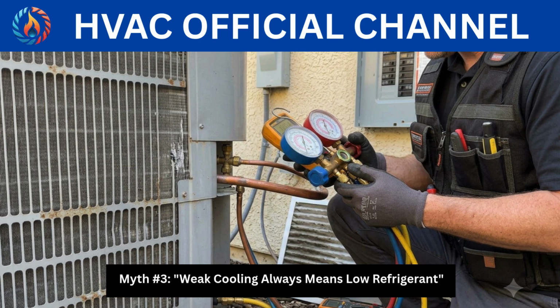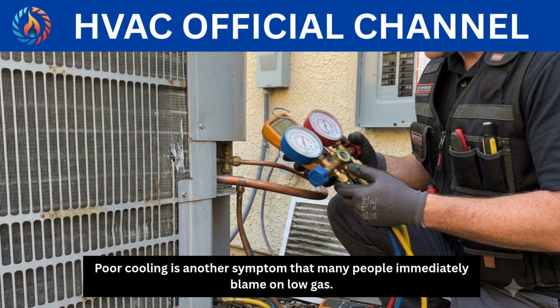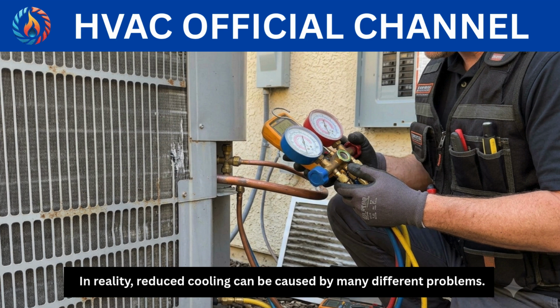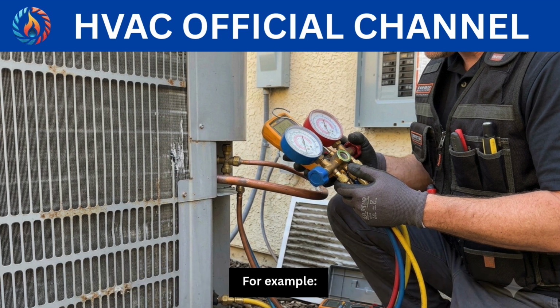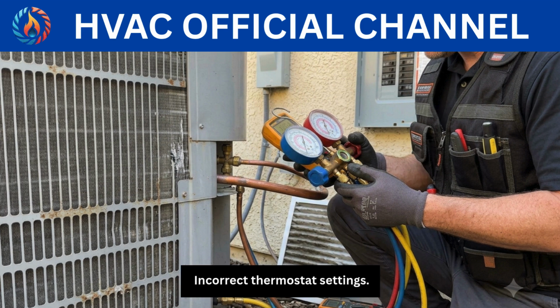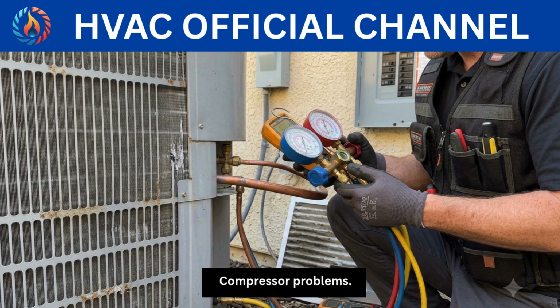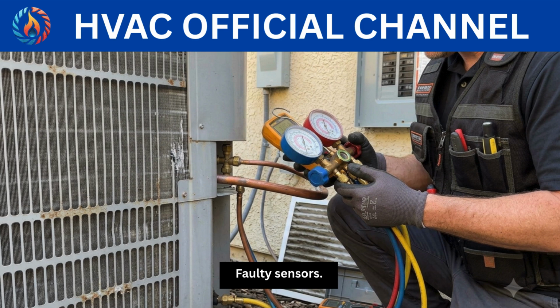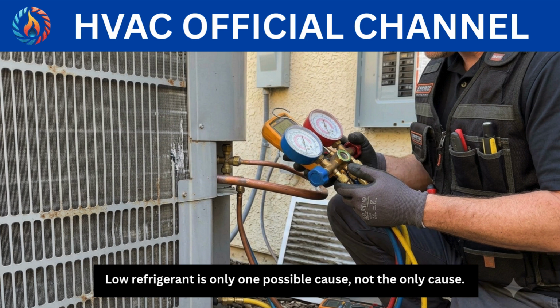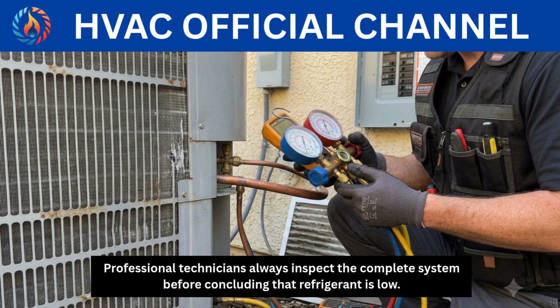Myth number 3. Weak cooling always means low refrigerant. Poor cooling is another symptom that many people immediately blame on low gas. In reality, reduced cooling can be caused by many different problems. For example, dirty condenser coils, dirty air filters, incorrect thermostat settings, weak capacitor, compressor problems, faulty sensors, electrical faults, blocked airflow. Low refrigerant is only one possible cause, not the only cause. Professional technicians always inspect the complete system before concluding that refrigerant is low.